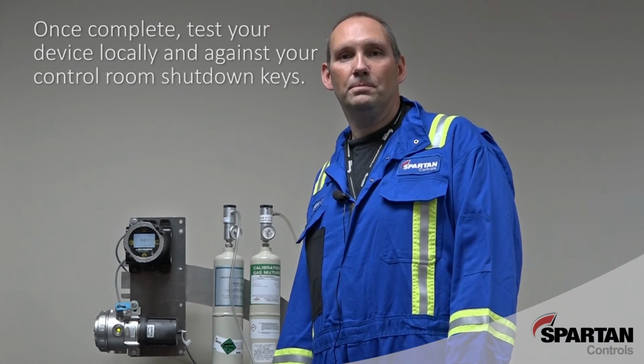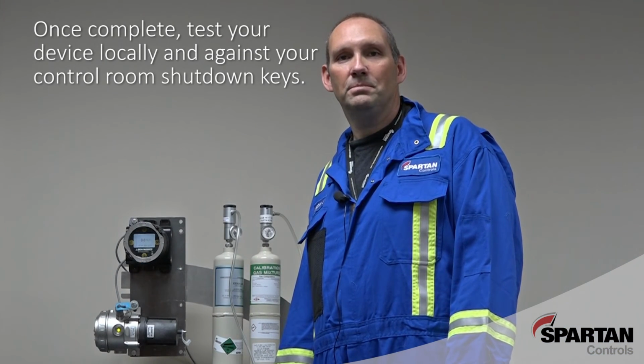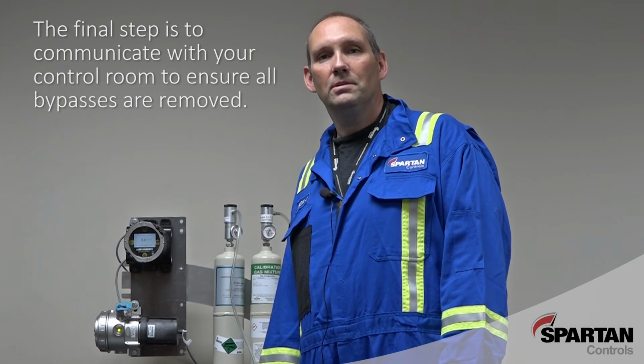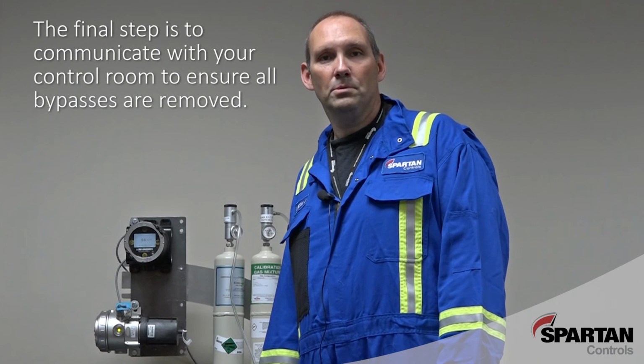Once your calibration is complete, it's important to test your device both locally and against your plant's shutdown keys. To complete your procedure, it's important to communicate with your control rooms to ensure all bypasses have been removed, as your device is good to go into service now.